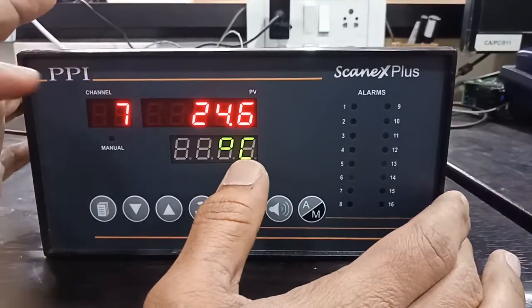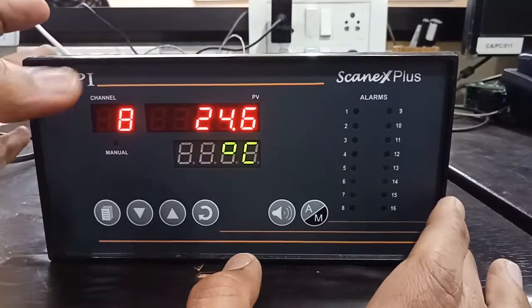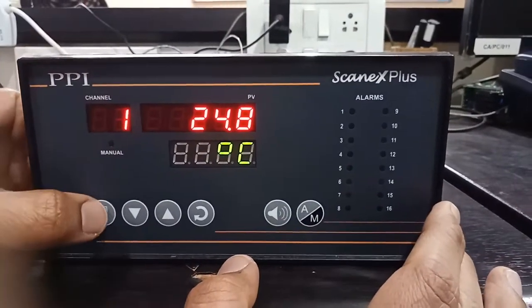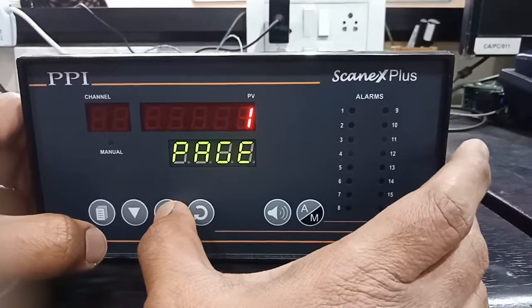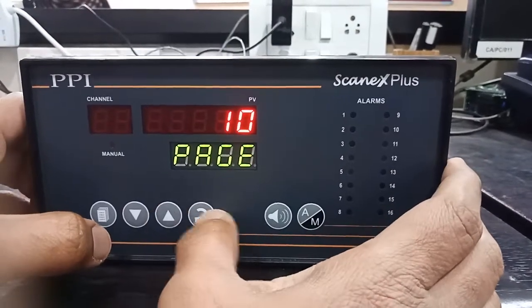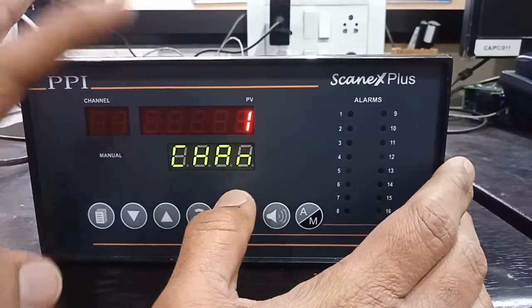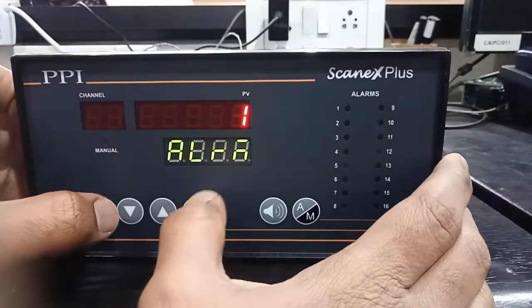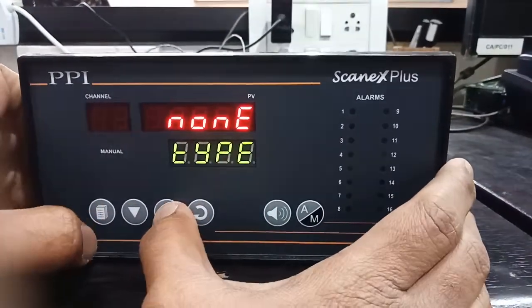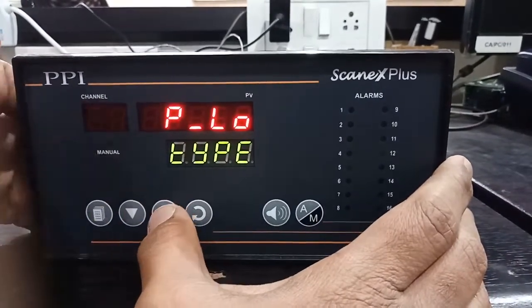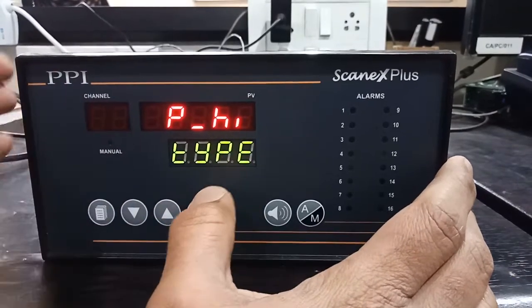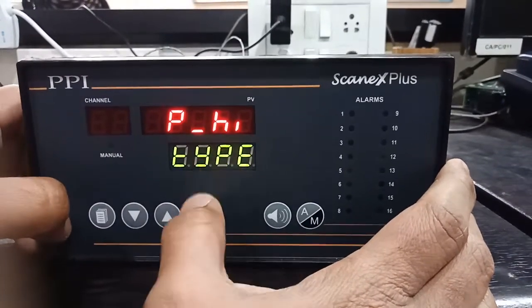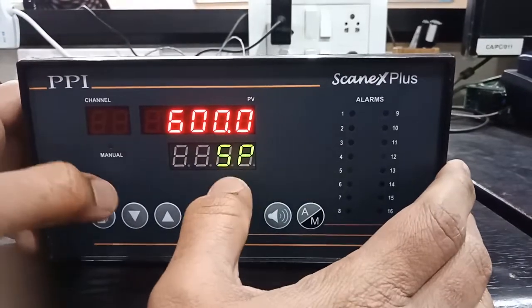Based on that input type, it will show you the PV values. To set the alarm mode, you have to go to page number 10. Select channel number 1, alarm 1, alarm type. If you want to select process lower or process high, you can set it based on your requirement. I have selected process high. Set the alarm setpoint.